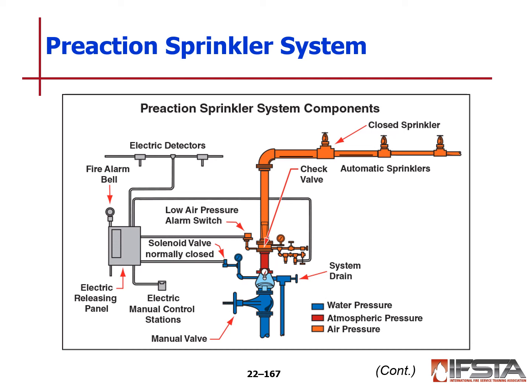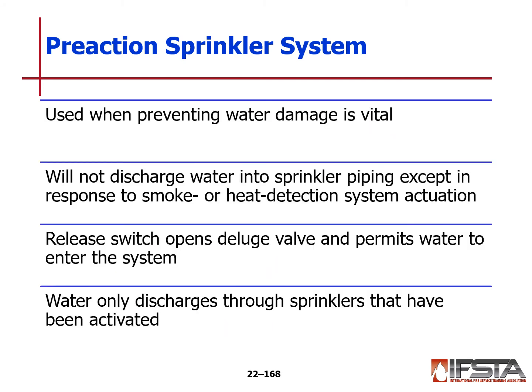Pre-action systems have a check valve and automatic heads. They're closed sprinkler heads, and you have a combination of water pressure, atmospheric pressure, and air pressure. These are used when preventing water damage is critical. They will not discharge water into the sprinkler piping except in response to smoke or heat detection in the system. The release switch opens the deluge valve and permits water to enter the system. Water only discharges through the sprinklers that have been activated.